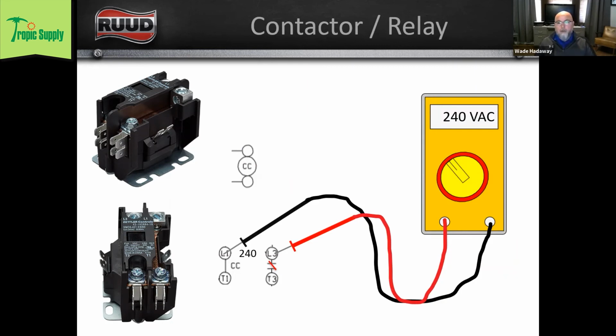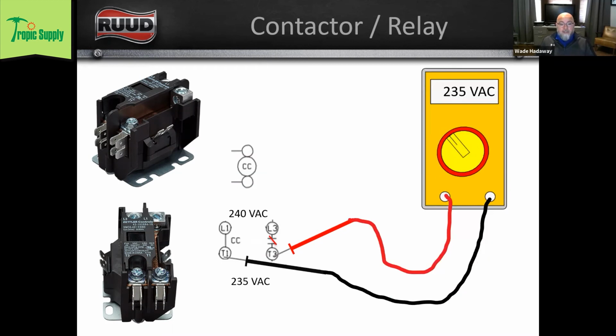And I know I'm measuring in absolutes, right? Most of the time when you check your low voltage, it's not 24 volts. And when you check your line voltage, it's not 230 or 240. They're not nice whole numbers. So we've got 240 volts coming in. But here in this example, we've only got 235 volts coming through on the load side of our contactor.